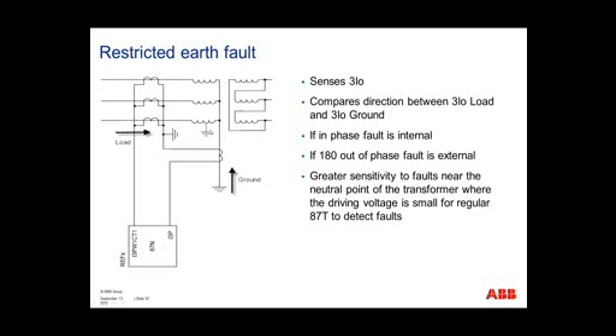However, when the fault evolves up one of the windings, there is going to be a flow of zero sequence current coming from this transformer, from this neutral point out of the transformer. The way that restricted earth fault protection works is you have your connections on the high side of the transformer, and you have a connection on the neutral leg of the transformer. You do a differential of your zero sequence current, either coming into the relay or coming into the transformer or leaving the transformer.